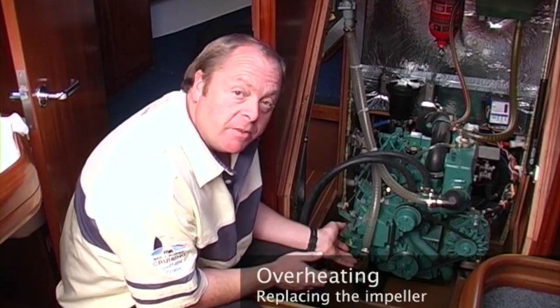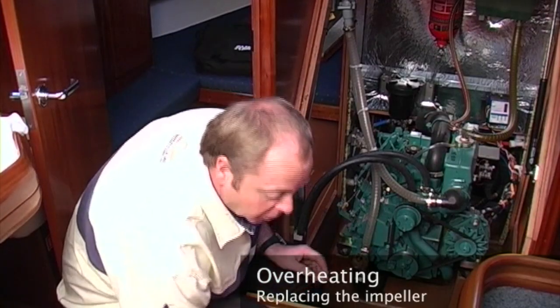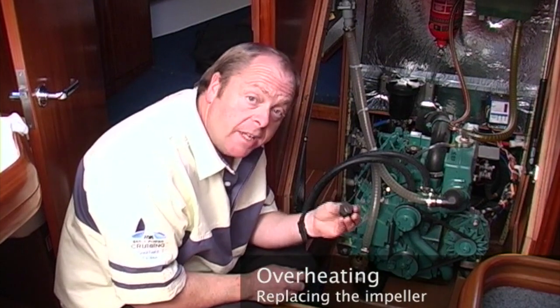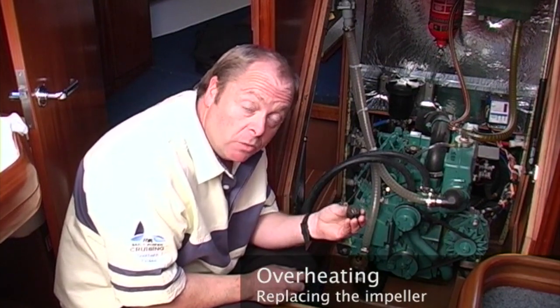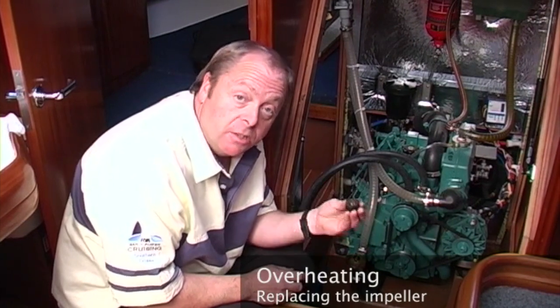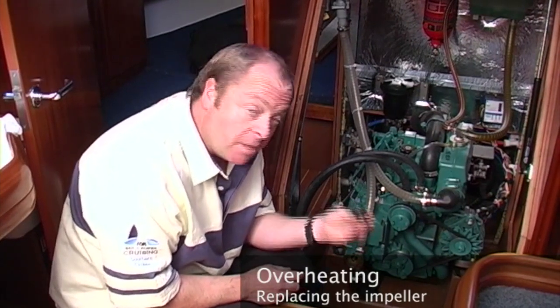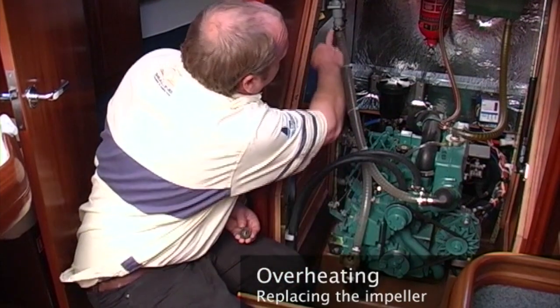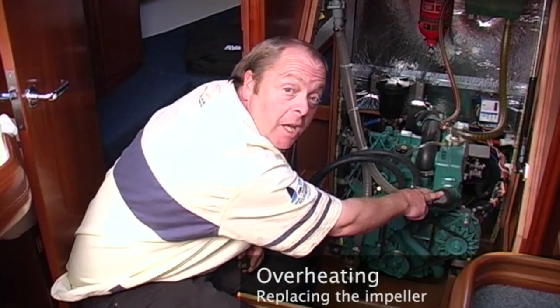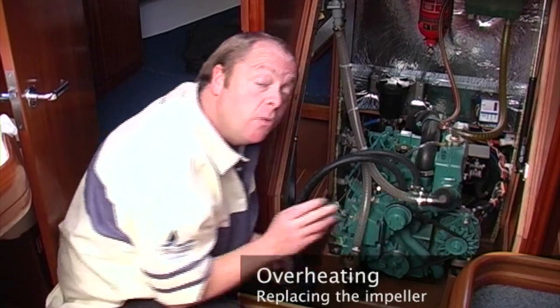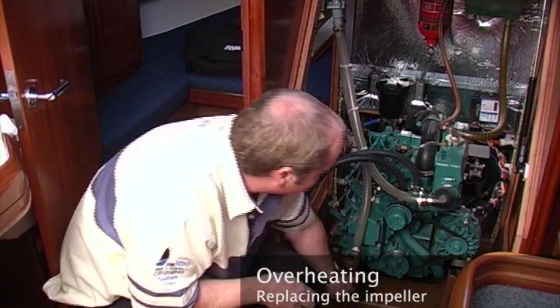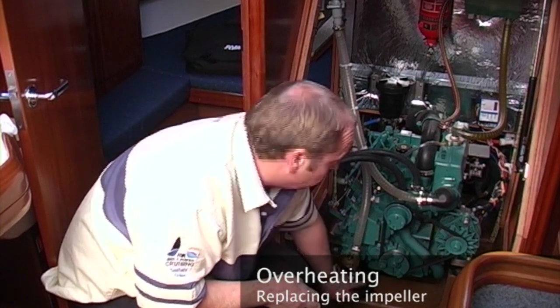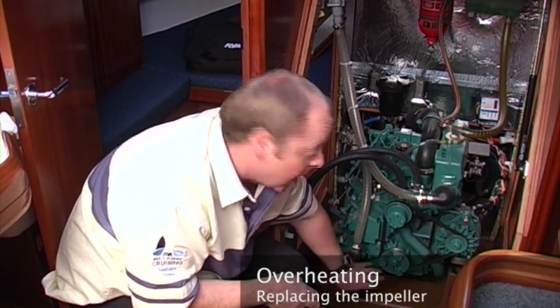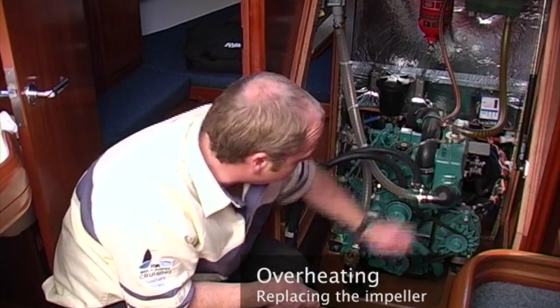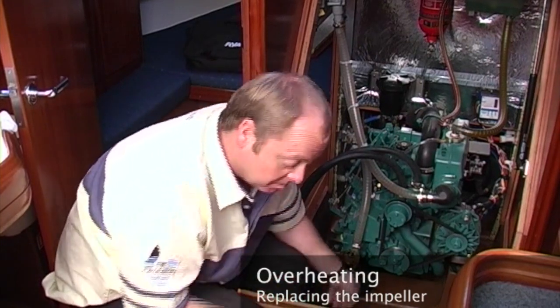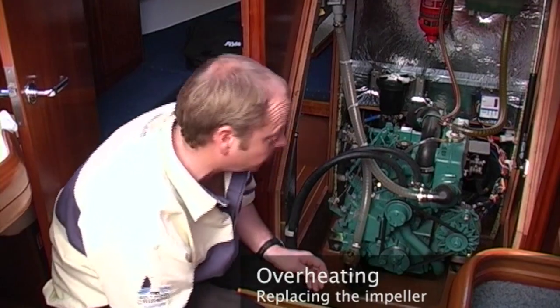Now, if when we opened up the faceplate the impeller looks something like this with all the blades missing, we need to find them all because they will be obstructing the cooling system. Some of the blades will carry on up here through the siphon valve and end up at the heat exchanger, but an awful lot of them will go back down the suction pipe here. So we would need to remove this suction pipe, flush the line through with some water, wash it all out, and try to catch as many of the blades as possible.